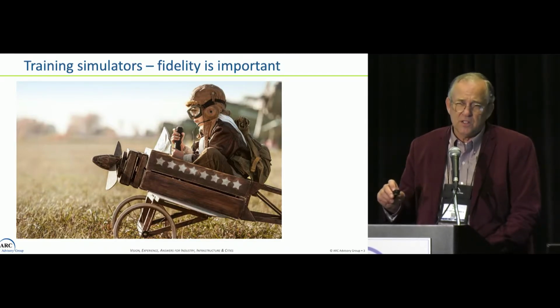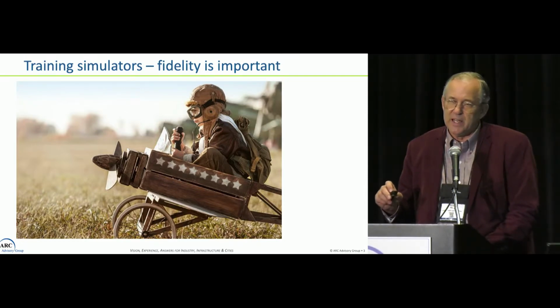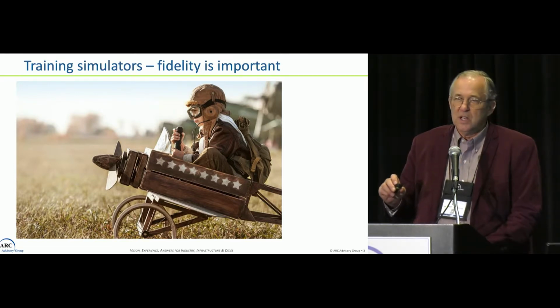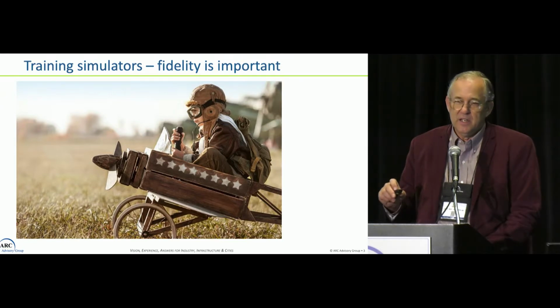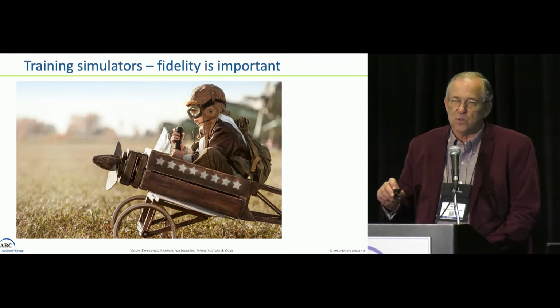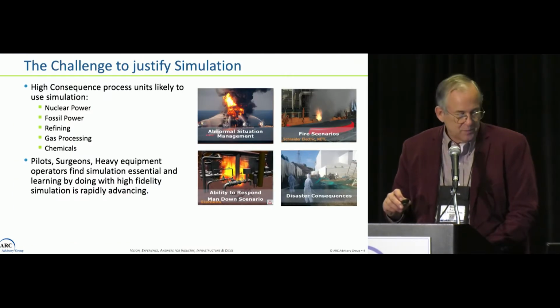But some of those models are just so good that you can use the models to tune controllers and then transfer those controller settings to the running plant. They use those models to do step testing for model predictive control and then use those model predictive controllers on the running plant. And when you're able to do that, you know that you have a good model. You can optimize these models and figure out the best operating points and transfer those set points to the controllers in the running plant, and those can achieve great financial results in many situations.